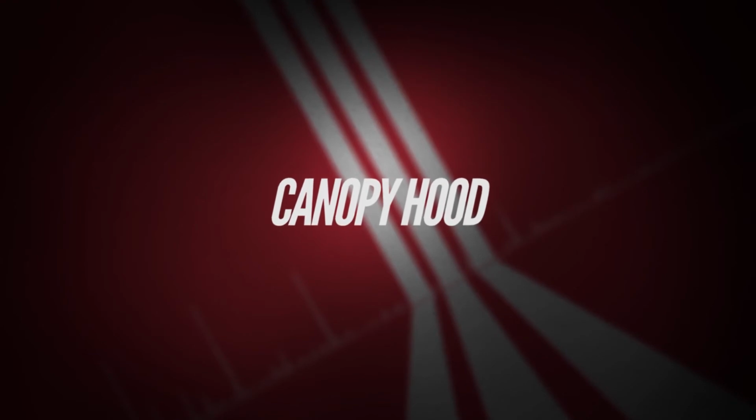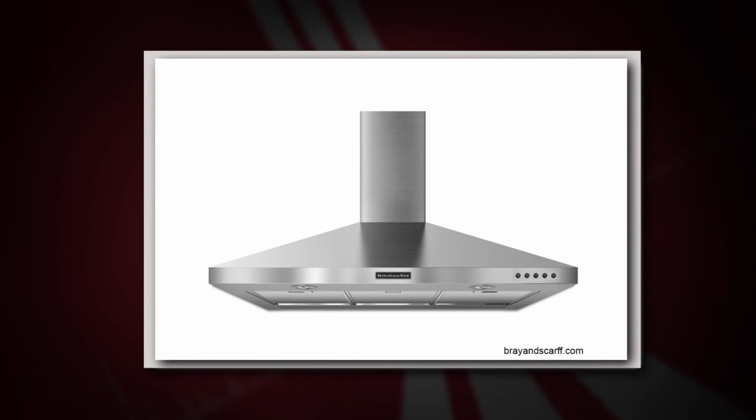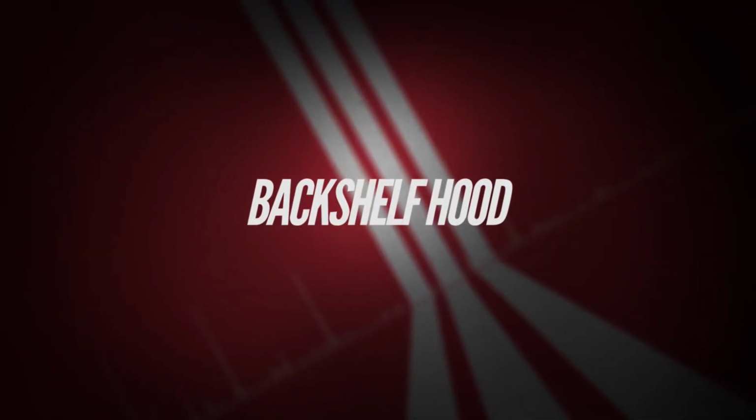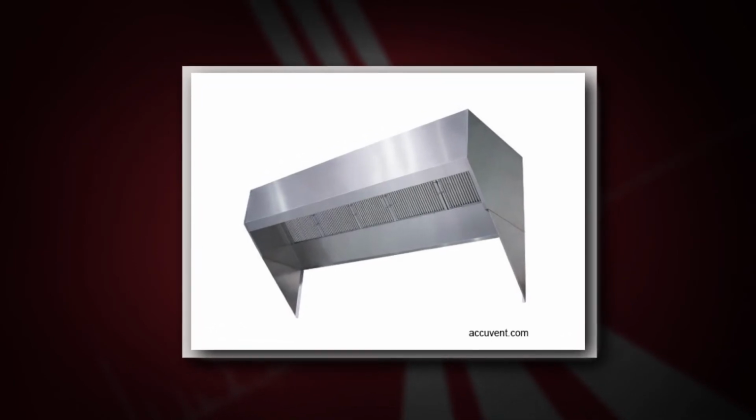This is probably the most recognizable hood, as it is the box-style hood that you see in most restaurants. E&O hoods, or exhaust-only hoods, are also the same style of hood, but they are usually Type 2 versus Type 1. Then we have backshelf hoods. This is the style you'll sometimes see in a short-order cooking application, where the hood is placed against the back wall and comes up at a 45-degree angle, and it's not hanging from the ceiling.